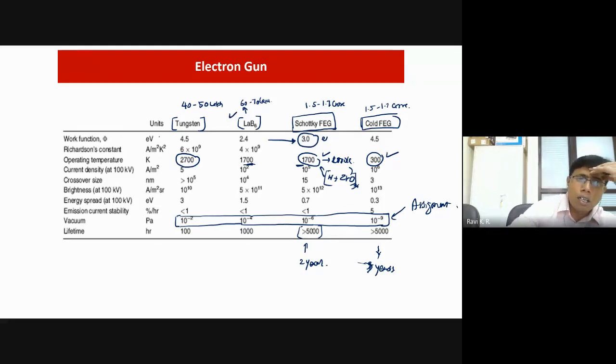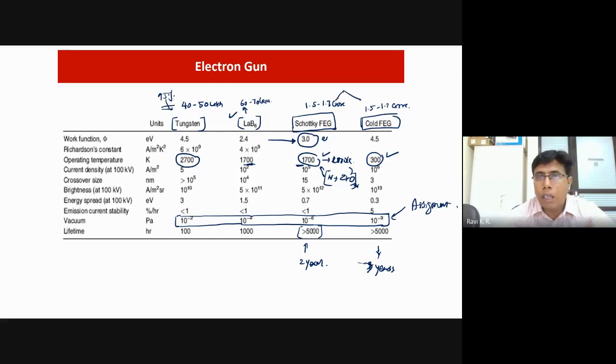But in general, worldwide, if you look at all conventional microscopes, they may be around 95%. If you compare all the FEG field emission gun machines, conventional may be around 90%, and this could be only 10%. Because this is actually the problem: vacuum level. For maintaining such a high vacuum level, your maintenance cost will be extremely high. So that is actually the problem.